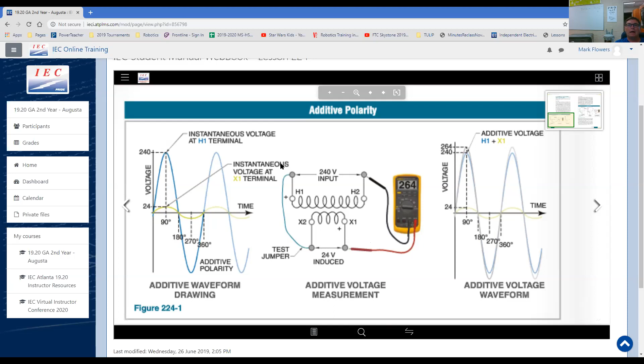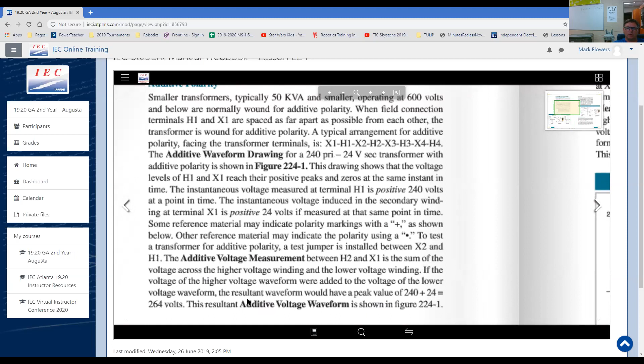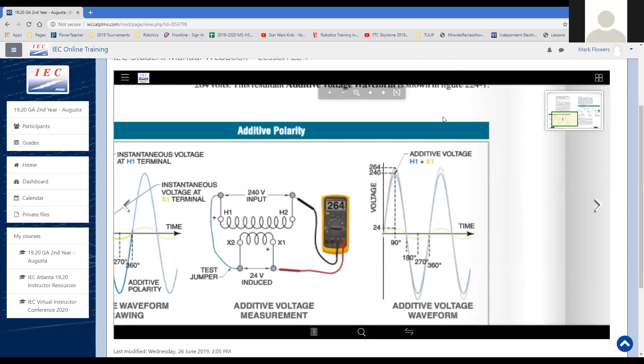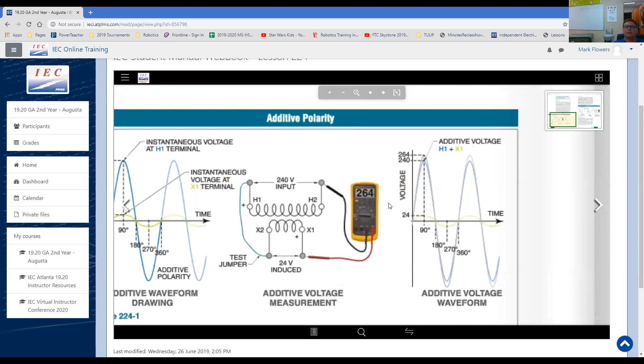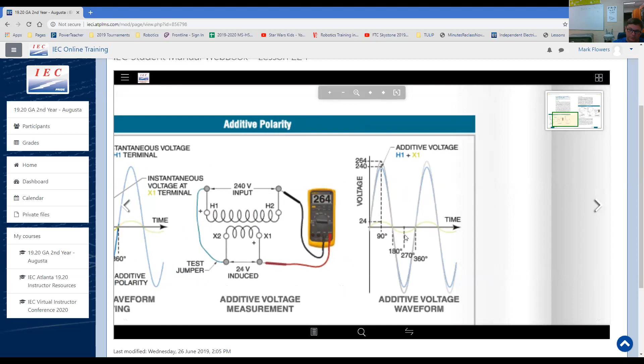What would be the point to have something like that? This voltage is induced in the secondary winding, and the terminal at X1 is positive 24 volts if measured at the same point, and it's the sum of the voltage across the higher voltage winding and lower voltage winding. If the voltage of the higher voltage waveform were added to the voltage of the lower voltage, the additive result will be 264 volts. You can see here the normal 240, but if we add it, our waveform gets a little bigger. We get that added boost, and that's what they call a boost of 24 volts.